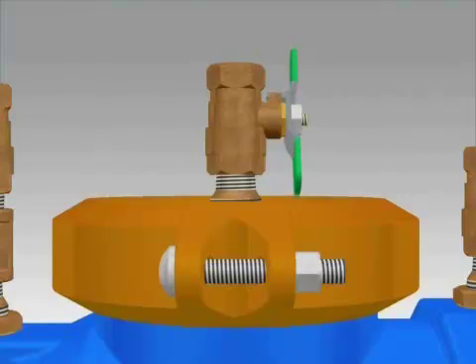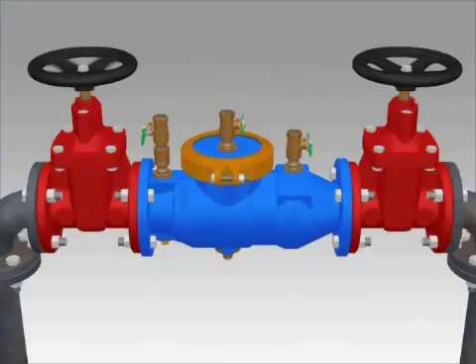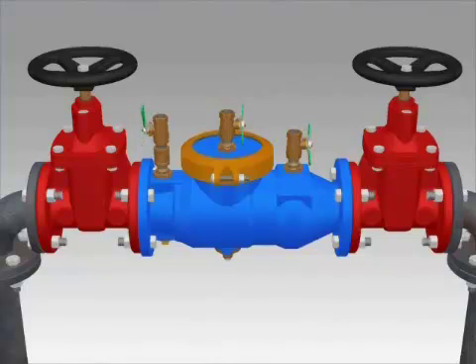Close the number 3 test cock. Open your inlet valve slowly to pressurize the assembly. Inspect for any leaks. Open and then close test cocks to bleed air from the assembly.